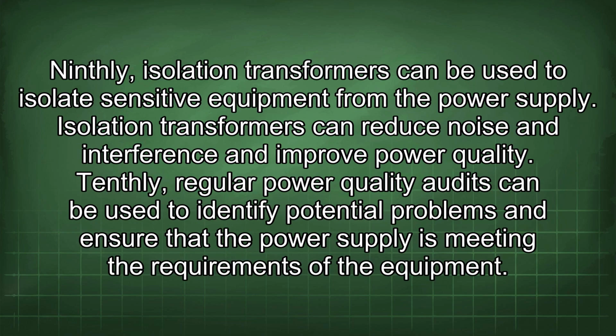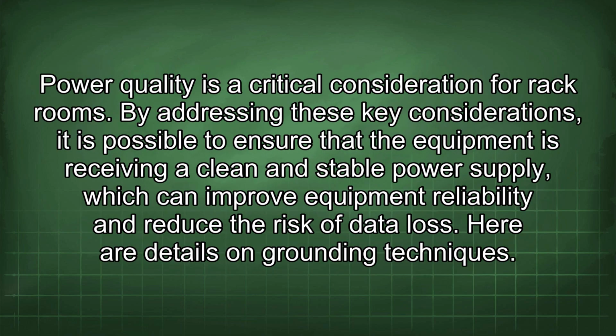Ninthly, isolation transformers can be used to isolate sensitive equipment from the power supply. Isolation transformers can reduce noise and interference and improve power quality. Tenthly, regular power quality audits can be used to identify potential problems and ensure that the power supply is meeting the requirements of the equipment. Power quality is a critical consideration for rack rooms. By addressing these key considerations, it is possible to ensure that the equipment is receiving a clean and stable power supply, which can improve equipment reliability and reduce the risk of data loss.